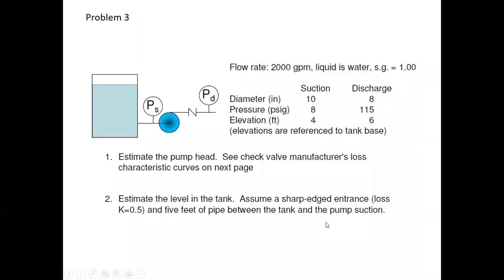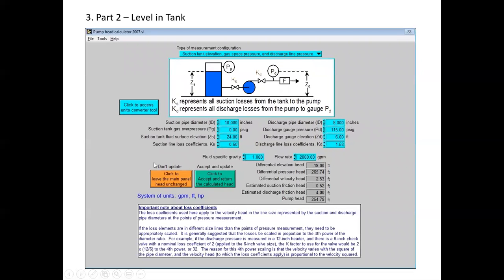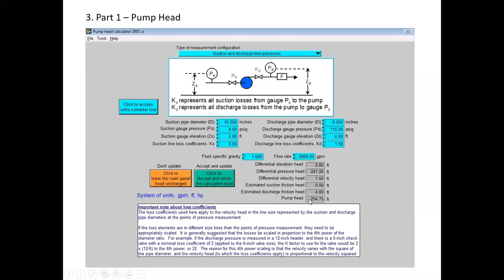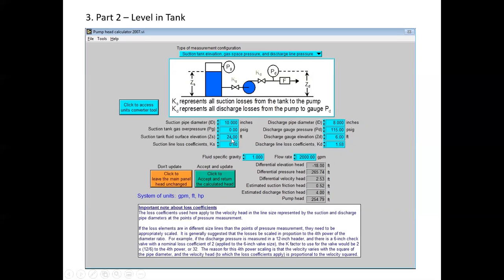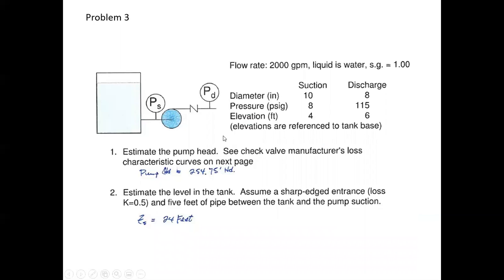So let's see, what was the first thing? So estimate the pump head, okay. So that's the pump head. Now we want to estimate the level in the tank. Okay, so we keep all this information the same, and basically what you do then is you change this tank level from this picture in order to have basically the same pump head. So it's pretty close. 254.75 is 254.79. I mean, you could shave a little off of this. But basically, this elevation is 24 feet in the suction tank. So that's pretty cool. Okay, and that just shows the information written in.